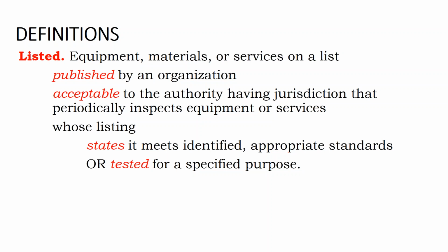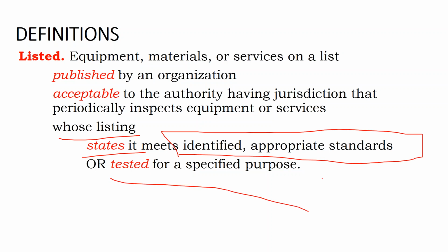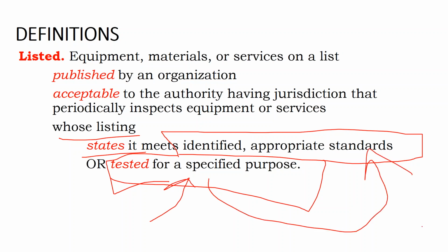Okay, so listing is a common requirement that can get confusing. You're required on job sites to use listed parts, and the most important thing about a listed part is that it's listed for a specific purpose, so that the listing states that it meets standards required for a certain purpose, or that the device has been tested for a specific purpose. Sometimes the need for the device comes out before a standard can be written for it. And so you might have a device that says it needs to be listed for a rapid shutdown standard. Sometimes the rapid shutdown products can come out before the standard is fully finished.